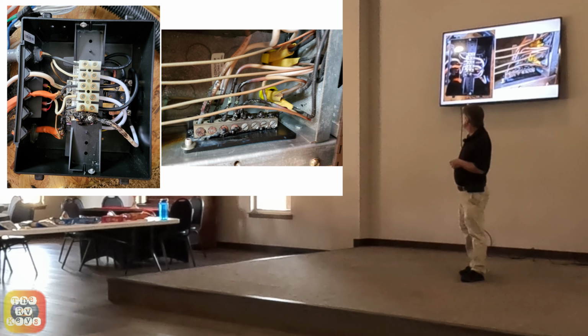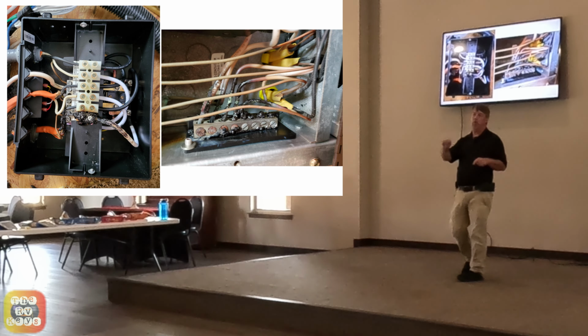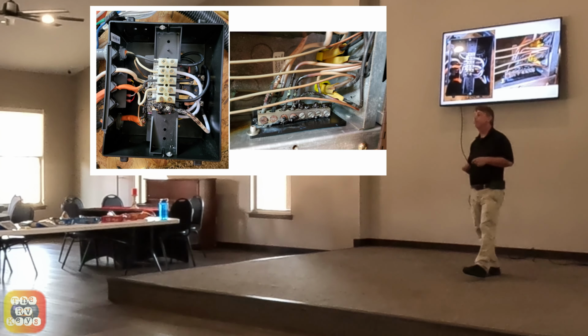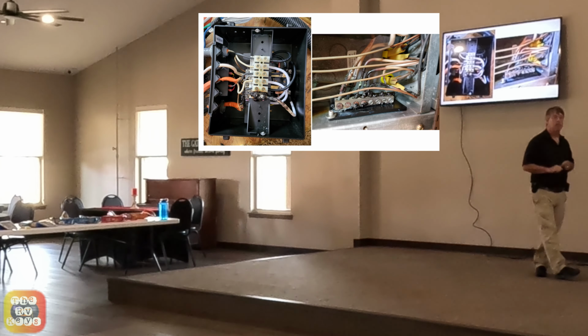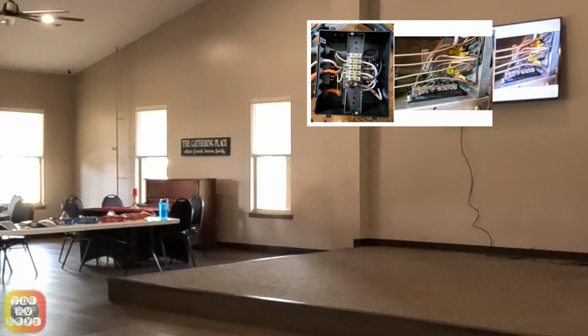They were definitely loose, so at least I was able to determine the likely cause of that failure. When we replaced this device, it was the same manufacturer, same model number, but they had switched to a clamp terminal that can't loosen like that, so it was definitely a solid solution.